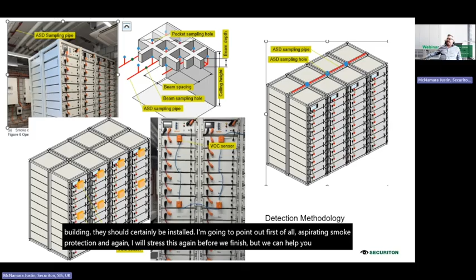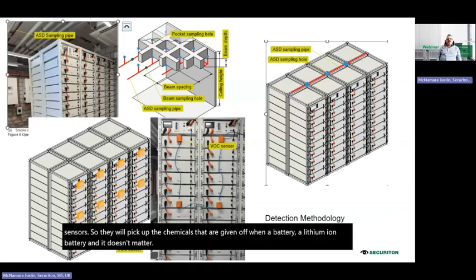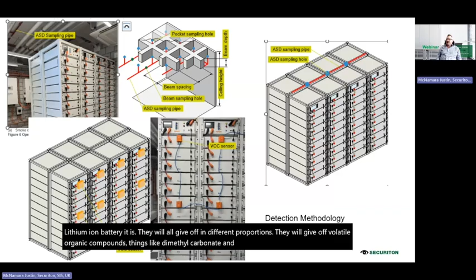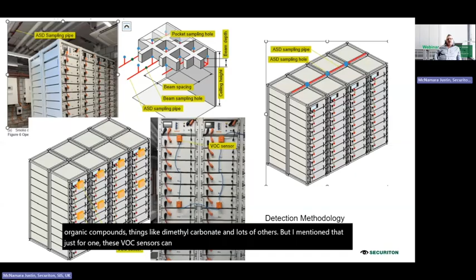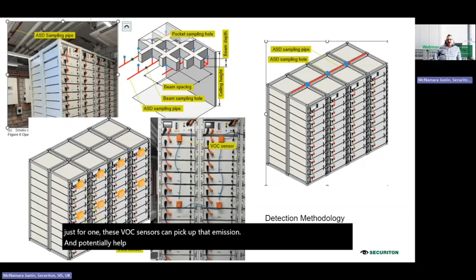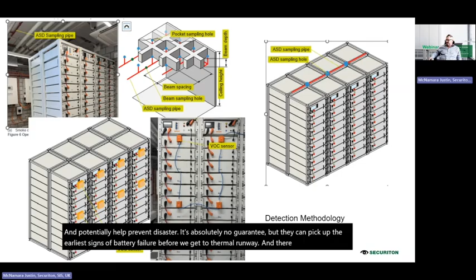You'll also notice some orange boxes here - these are the VOC sensors I mentioned, volatile organic compound sensors. They pick up the chemicals given off when a lithium-ion battery fails, and it doesn't matter which make or manufacturer, they'll all give off, in different proportions, volatile organic compounds like dimethyl carbonate, among others. These VOC sensors can pick up that emission early and potentially help prevent disaster. It's absolutely no guarantee, but they can pick up the earliest signs of battery failure before we get to thermal runaway, and there may be mitigation we're able to adopt at that point.